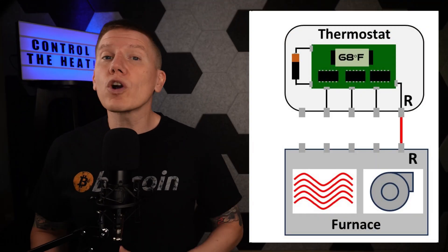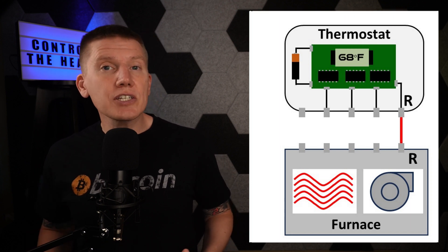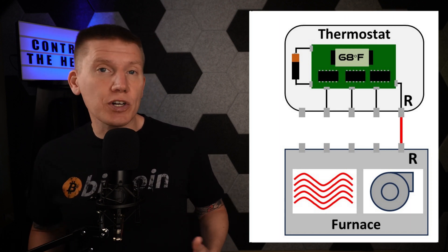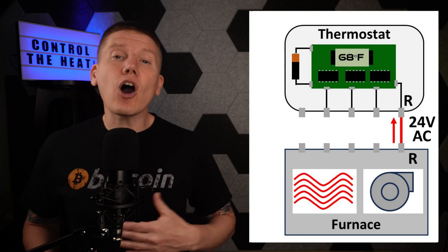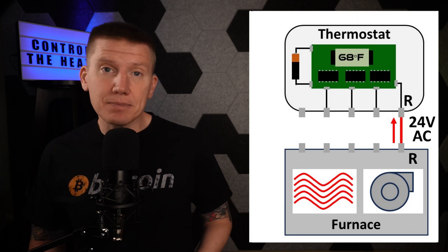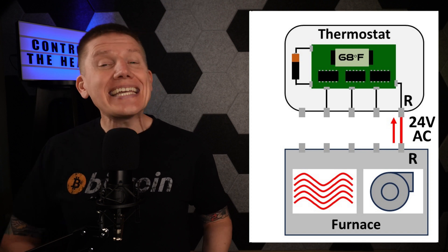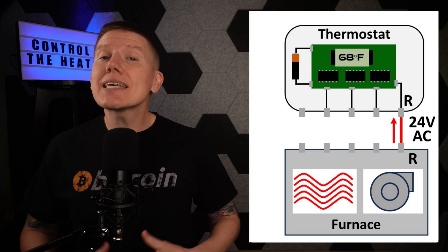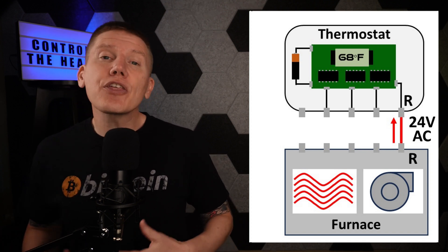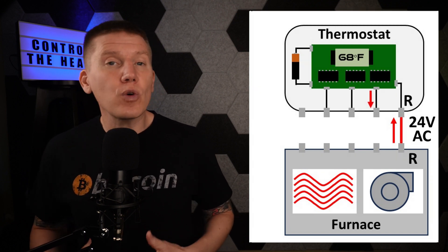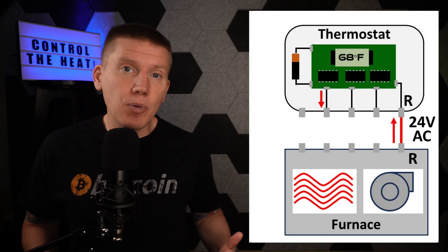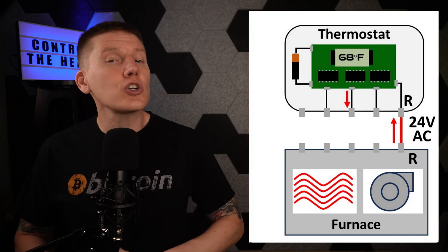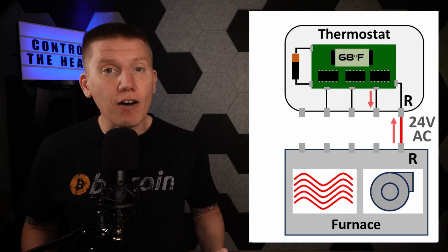The first of these four wires is the R or red wire. The R connection on the furnace is the source of the 24-volt AC power used to control the furnace and other parts of the HVAC system. This 24-volt source is sent to the thermostat, which has a matching R terminal, and the thermostat then routes that 24-volt AC power to the other wires going back to different components of the HVAC system, controlling what gets turned on and off.